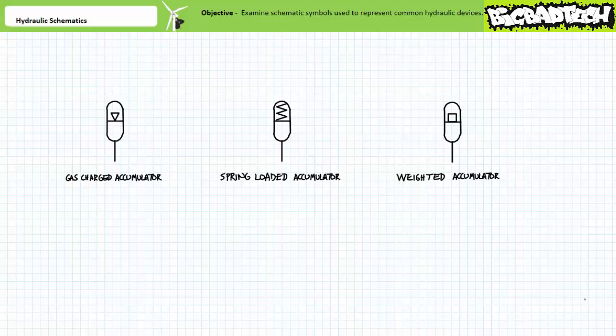The good news is the stored energy in an accumulator can be used when a system undergoes an emergency shutdown. The bad news is an accumulator can also be a source of hazardous stored hydraulic energy. Part of proper lockout and tagout procedures often necessitate that accumulators be discharged prior to beginning any work. Any technician working on a system with a charged accumulator runs the risk of being injured or killed by the stored hydraulic energy. Spring-loaded accumulators swap out the gas-charged symbol for a spring. Weighted accumulators swap out the spring symbol for a big block.